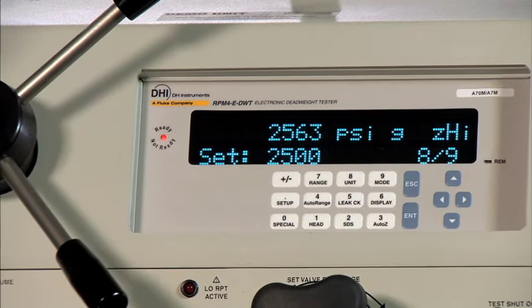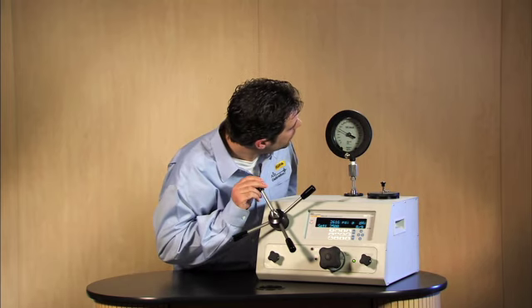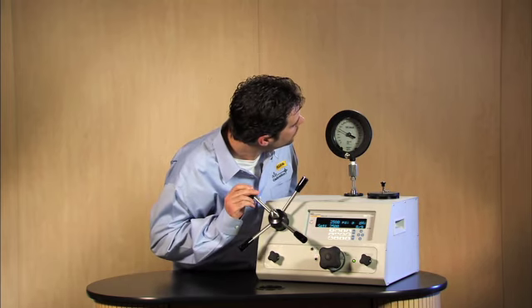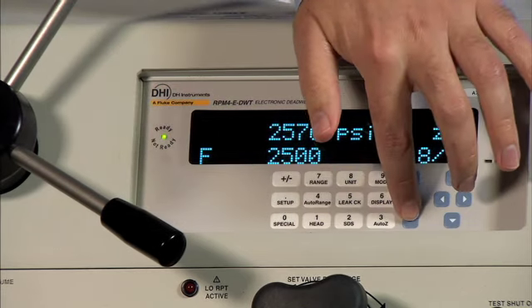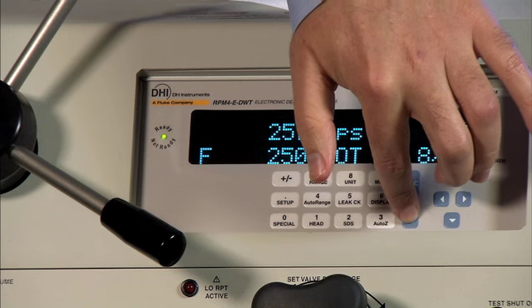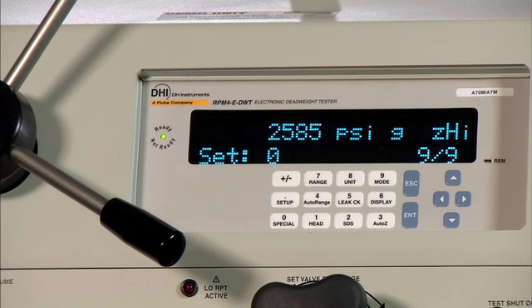At 2,500 psi. Wait till it's green. Make a slight adjustment because it has gone up in pressure slightly. It's green. Go ahead and press enter. This one is out of tolerance. Push enter. Now it says to set zero pressure.